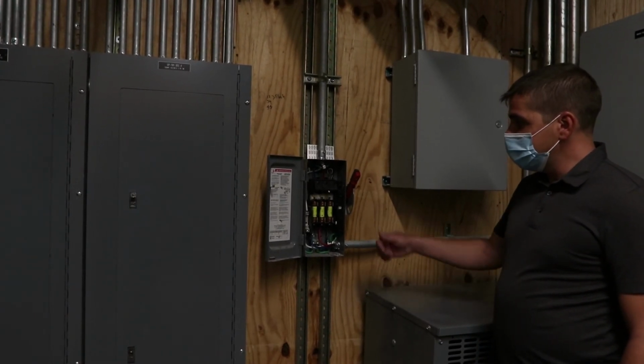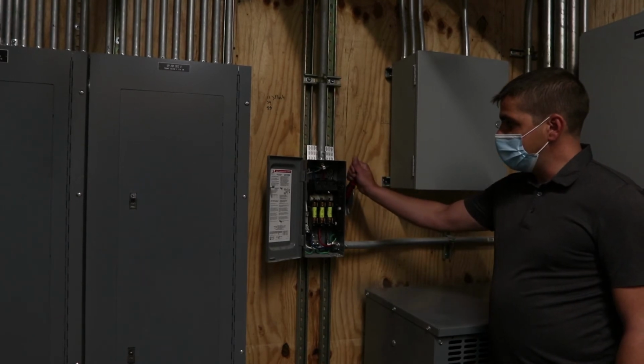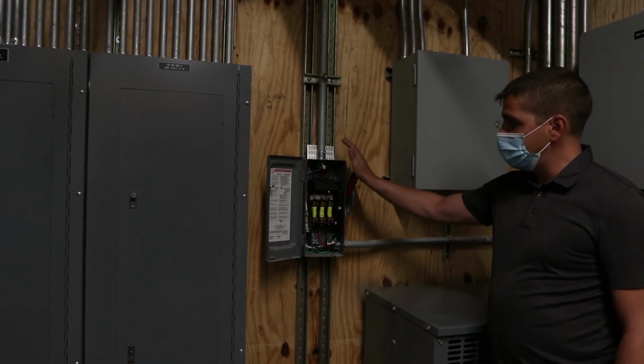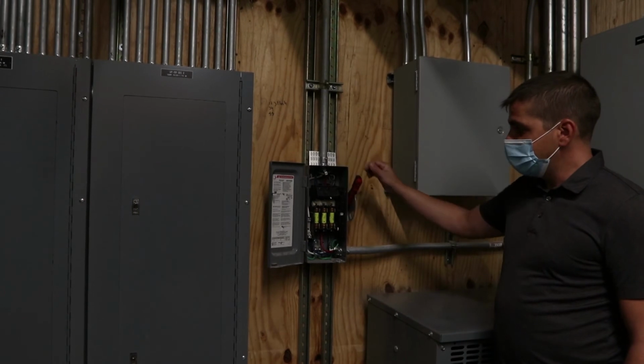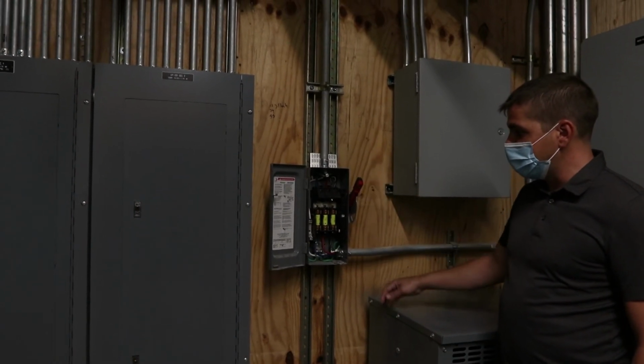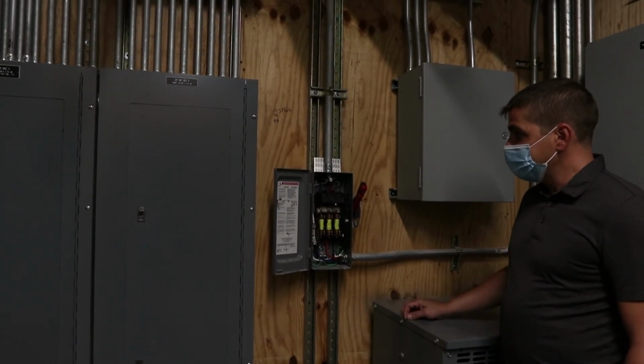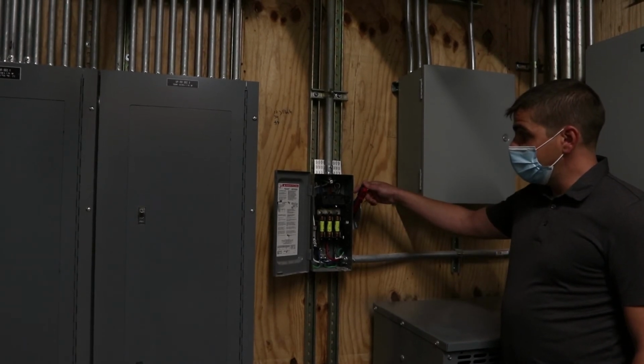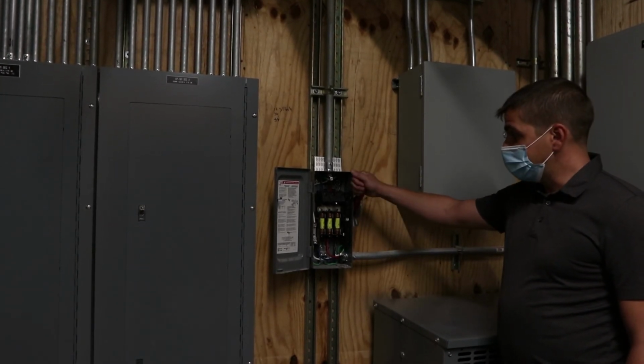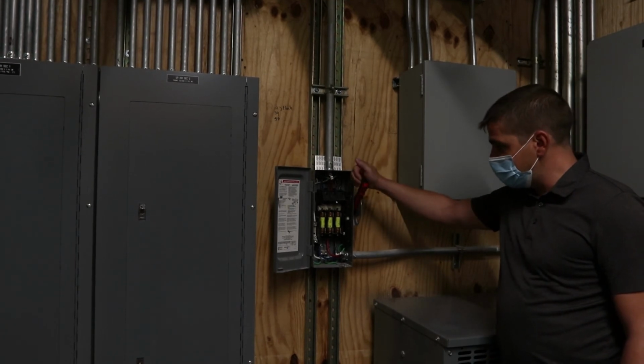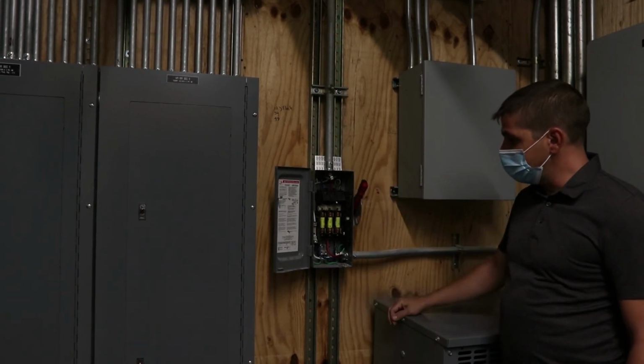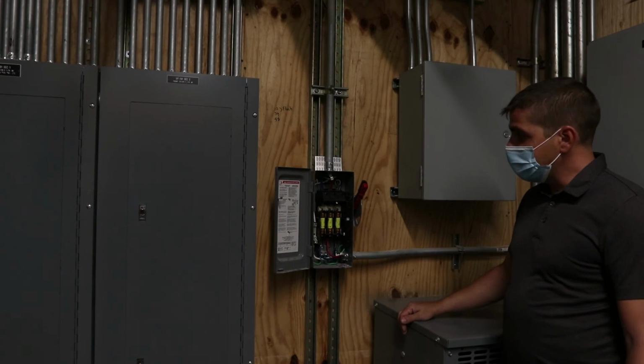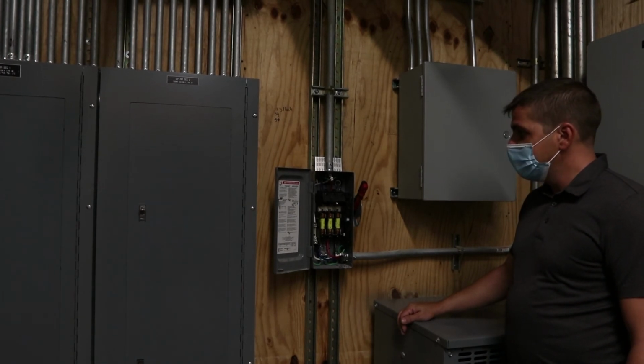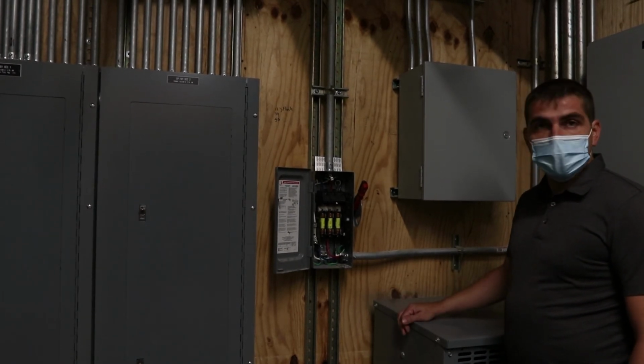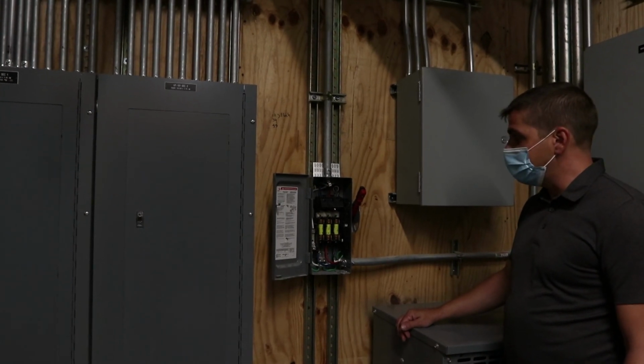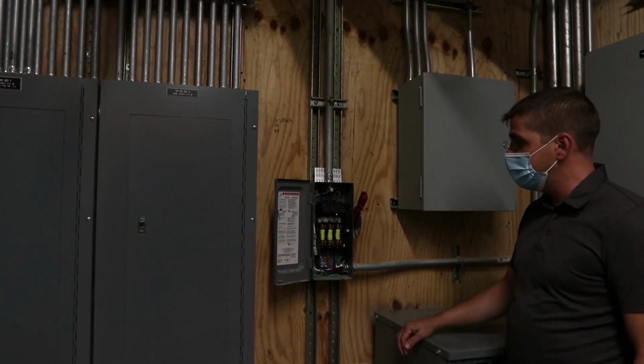When the fuse is installed and the disconnect switch is in the on position, which is the handle in the upper position, you have to use a tester to make sure that power is supplied to the equipment, and that's it. Anytime it has to be serviced, the equipment has to be in the off position, which means this handle in the bottom position, before it can be serviced. It does not require any specific maintenance. If the equipment loses power, that means there's something wrong with the fuse link here. That's it.